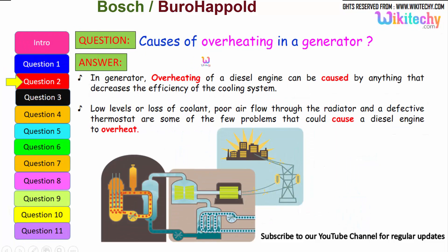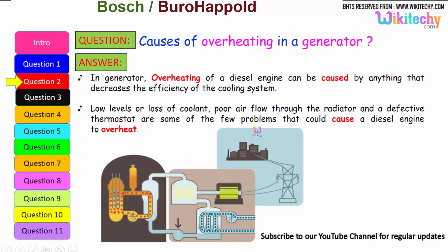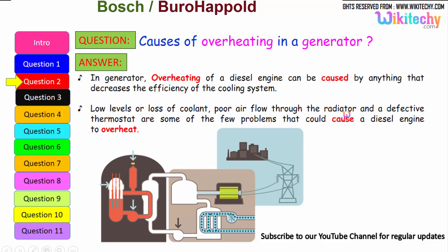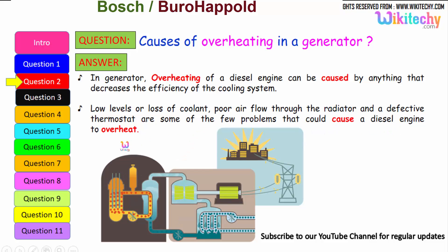Let us move on to the next question: causes of overheating in a generator. Overheating of a diesel engine can be caused by anything that decreases the efficiency of the cooling system. It can be due to loss of coolant or low levels of coolant, poor airflow through the radiators, and a defective thermostat — some of the few problems that could cause a diesel engine or generator to overheat.